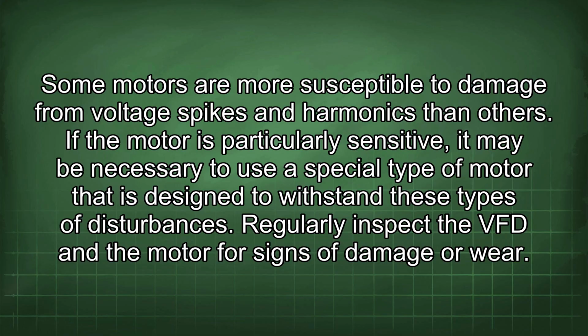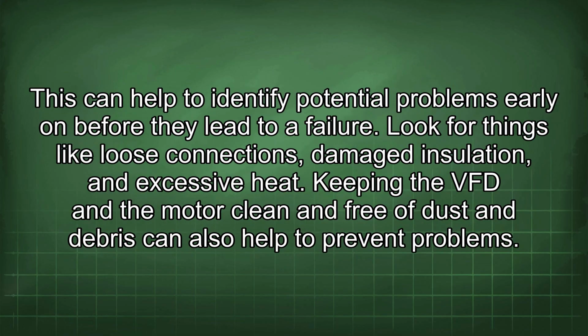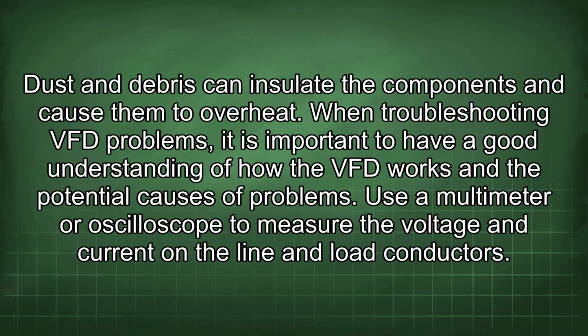Regularly inspect the VFD and the motor for signs of damage or wear. This can help to identify potential problems early on before they lead to a failure. Look for things like loose connections, damaged insulation, and excessive heat. Keeping the VFD and the motor clean and free of dust and debris can also help to prevent problems. Dust and debris can insulate the components and cause them to overheat.